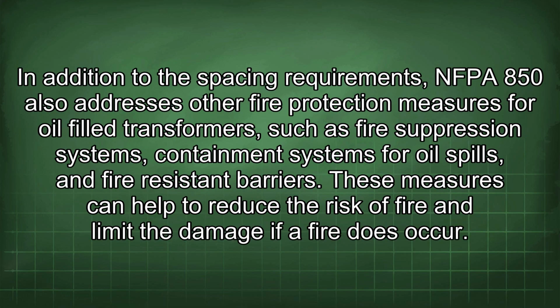In addition to the spacing requirements, NFPA 850 also addresses other fire protection measures for oil-filled transformers, such as fire suppression systems, containment systems for oil spills, and fire-resistant barriers. These measures can help to reduce the risk of fire and limit the damage if a fire does occur.